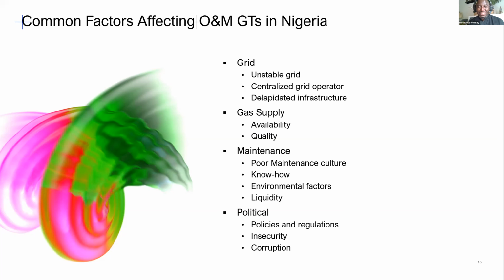Then there are environmental factors. For instance, most of the gas turbines are in the Niger Delta area, close to the sea, so the quality of air coming into the gas turbine has a lot of salty air, sodium chloride, which reacts with the super alloys used in the design of the compressor. So you have fouling, pitting, and other kinds of corrosion that happen due to those chemical reactions.